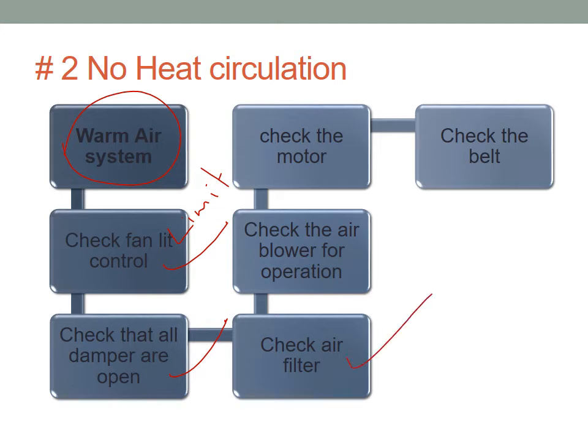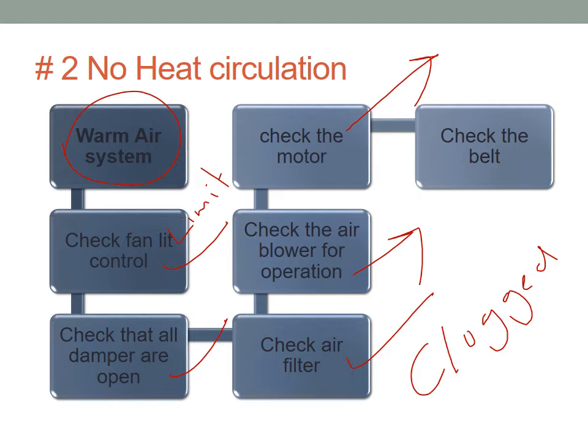Check the air filter if it's clogged. Check the air blower for operation. That's the inducer fan. And check the motor, make sure it's running. We had an issue with the motor in the lab as well where the motor was wired incorrectly. Check the belt for tension.